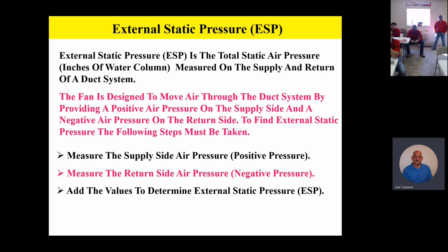So to measure external static pressure, or ESP, you're going to measure the supply side static pressure, which is going to be a positive number, and write that down and remember it. You're going to measure the return side static pressure and write it down and remember it. Then you add those two values together to get what we call external static.